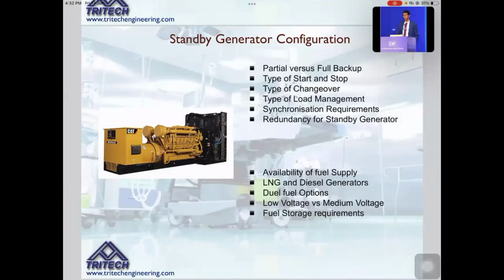Load management means, suppose you have a series of generators and you may not be needing all the generators at the same time. So depending on whatever your load is, you will be switching on. And what system you have for switching on, whether it's manual or automatic, is another option. Then we have the synchronization. Basically, when you're paralleling the generator, it's called synchronizing. So synchronization of generators is another aspect you need to look at when you're looking at the generator configuration. And again, the percentage of redundancy, like what generator you're willing to invest in, keeping it as a redundant standby.